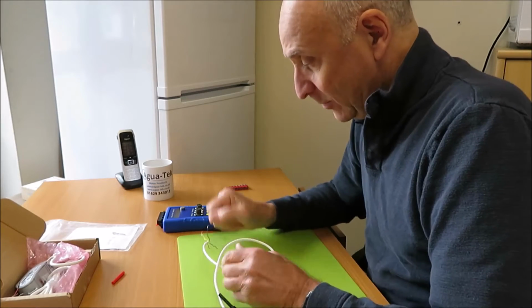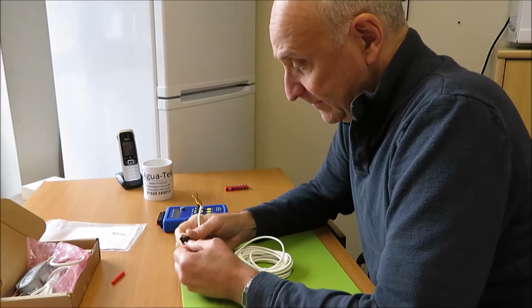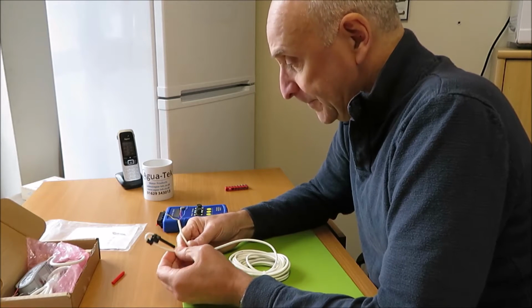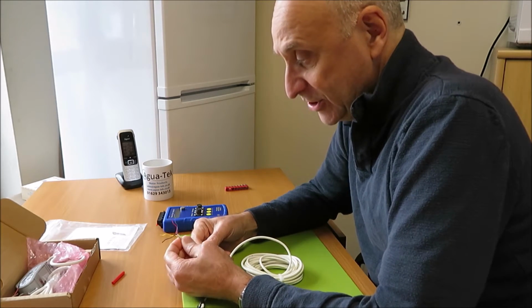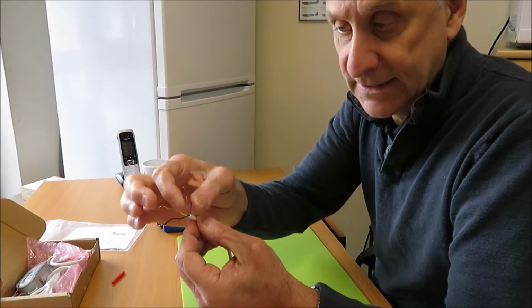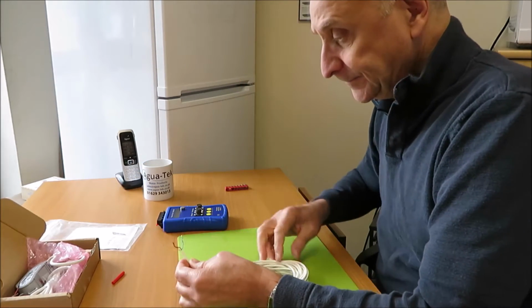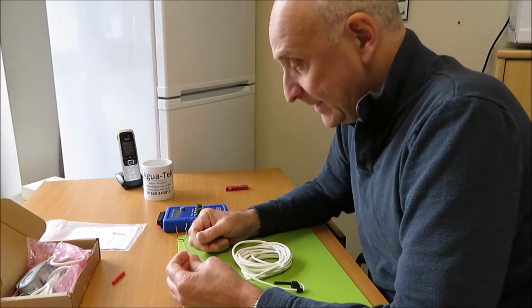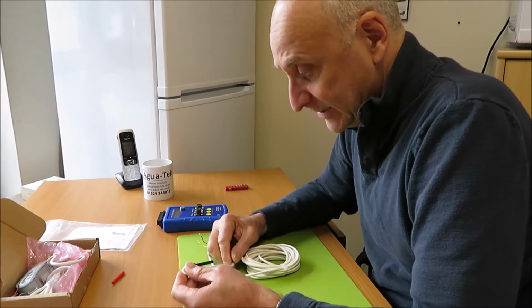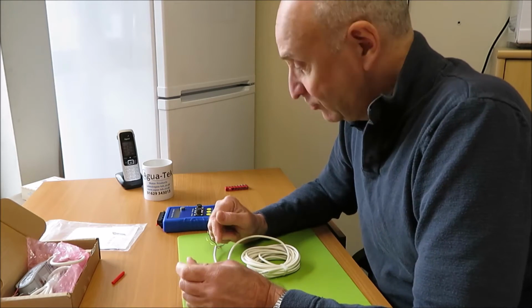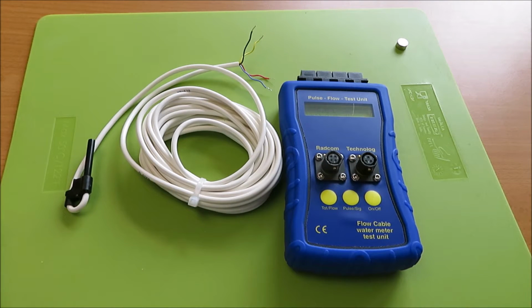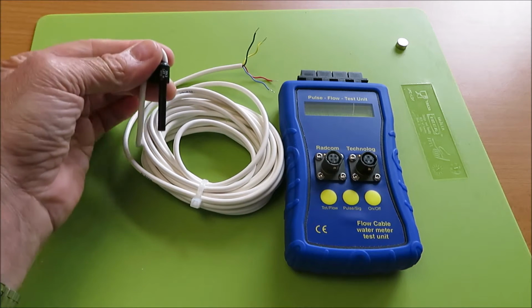Now, I happen to know on the V100 T-Probe that the actual wire connections to use are actually the red and the blue, and I'll demonstrate how I test this particular flow sensor in a second. I'll just reposition the camera to give you a better view. Okay, now I've repositioned the camera, I'll demonstrate which wires and where to put them into the pulse test unit to test the T-Probe flow sensor here.